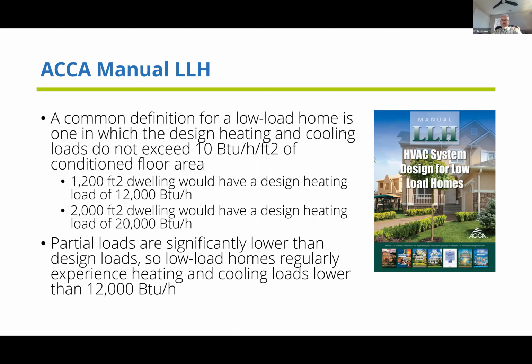So just to give you a couple examples, a 1,200 square foot dwelling, which I built a lot of when I was at Habitat, would have a design heating load of around 1 ton. And a 2,000 square foot dwelling would have a design heating load of somewhere around 20,000 BTUs - just under 2 tons, or just over 1.5 tons.